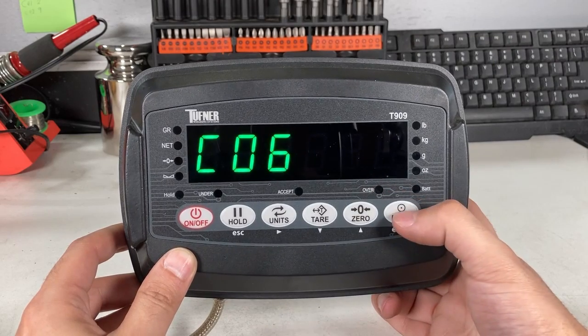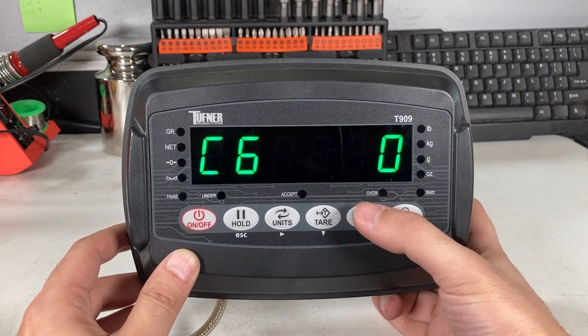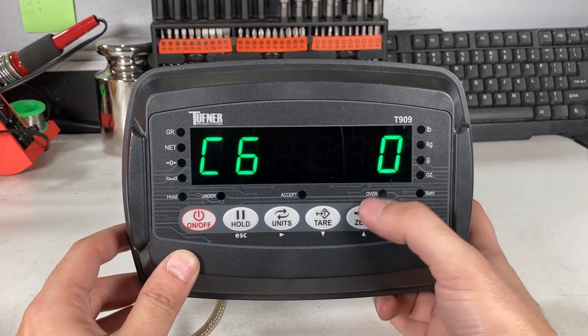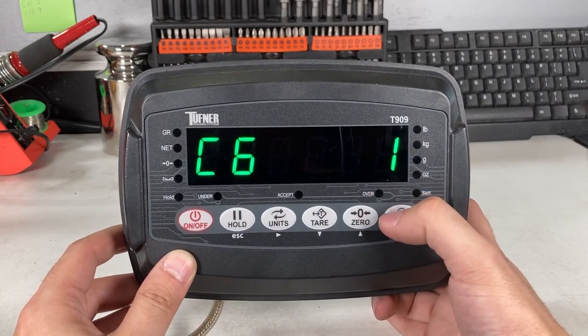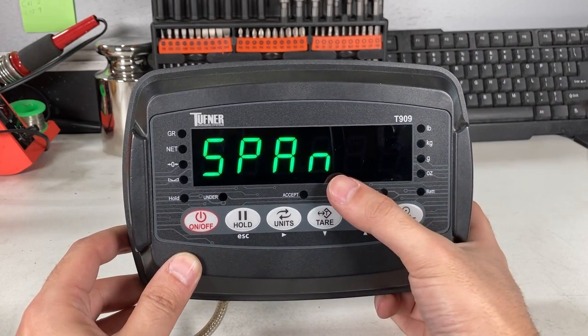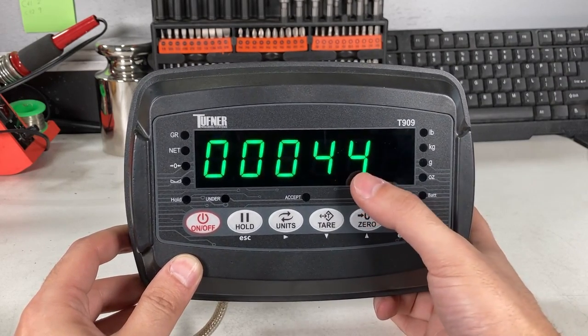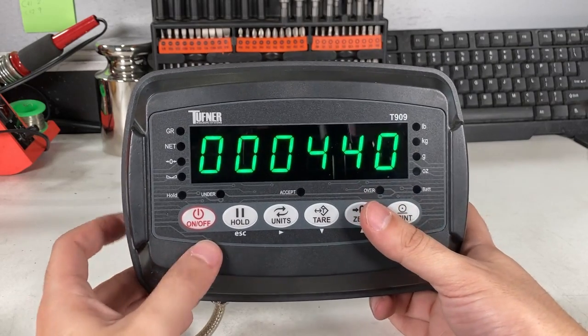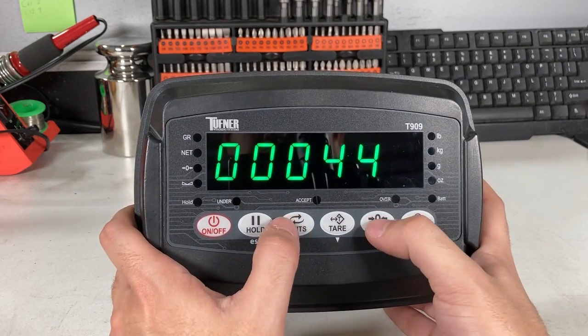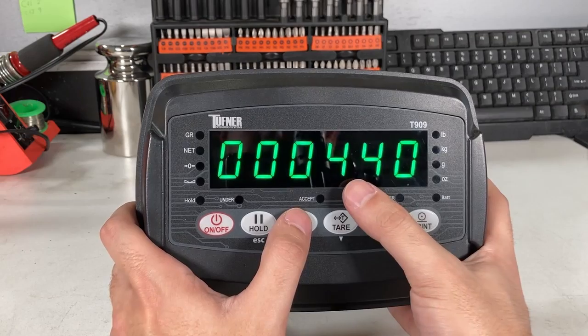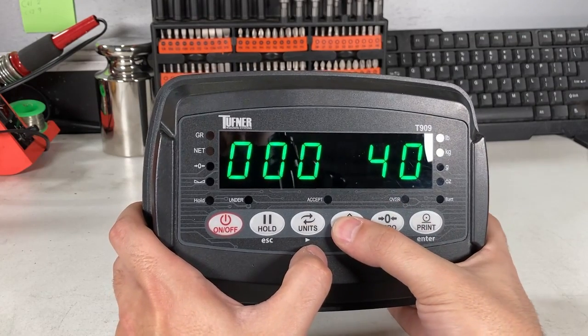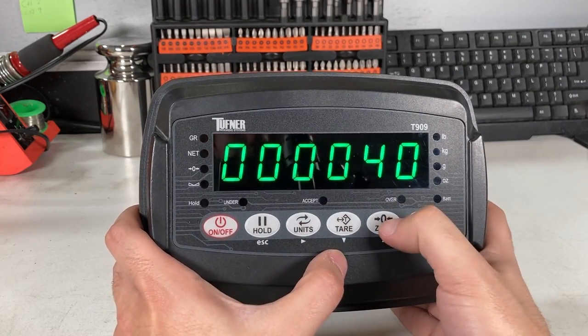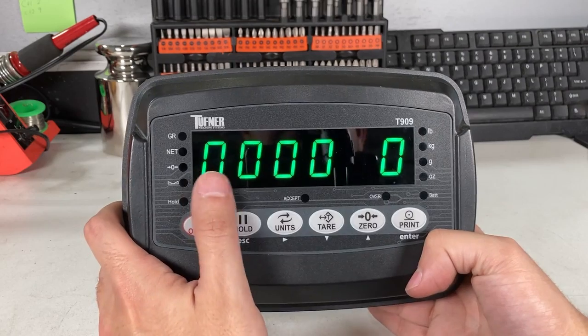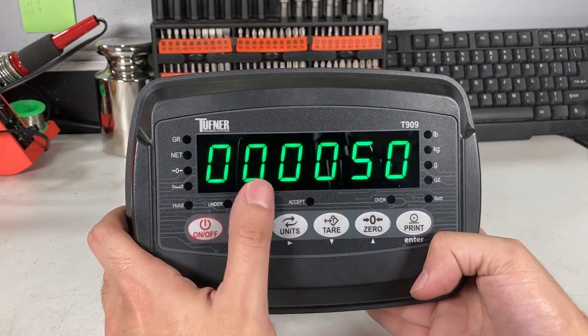C06. Now at C06, press print. C60, so to get into the menu, you make that 1. C61, and you press print. You'll see span, and now you see weight for calibration. In my case, I'm going to use 50 pounds, so I'm going to make the 100s place 0 and make this 5. Whatever weight you're going to use for calibration, you dial in now.